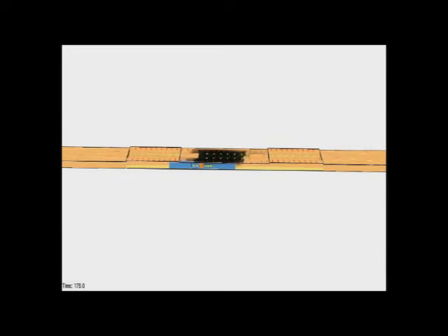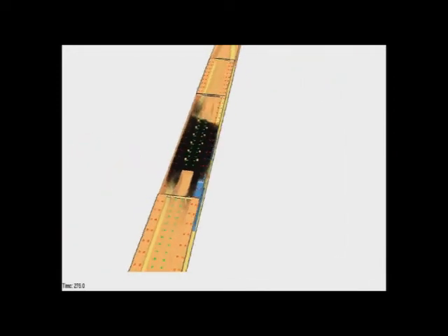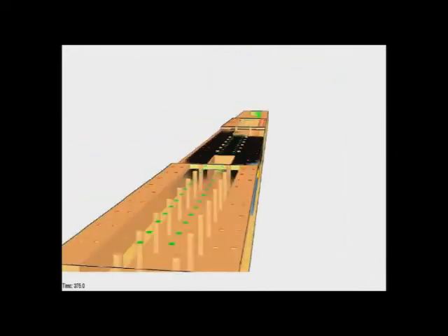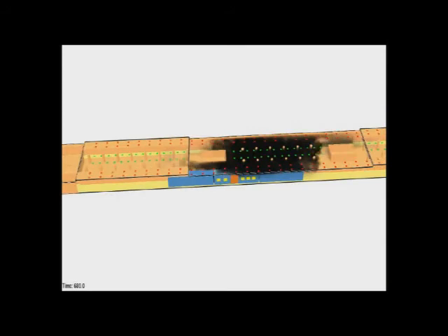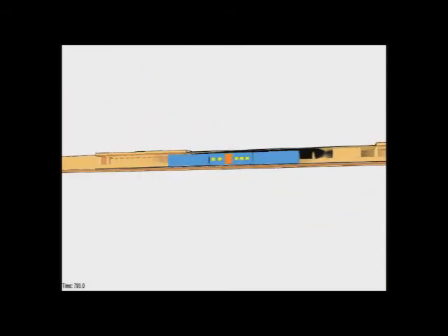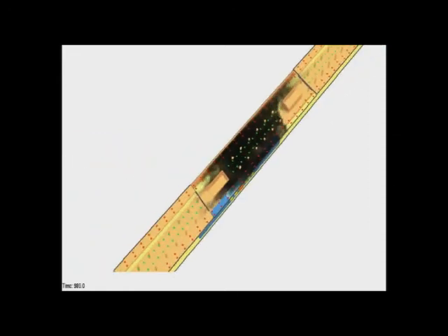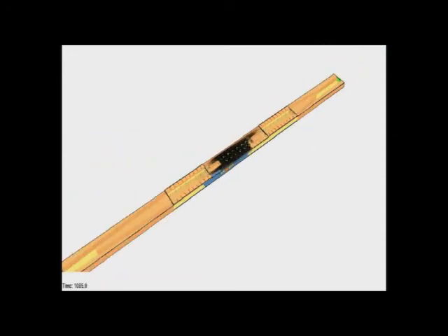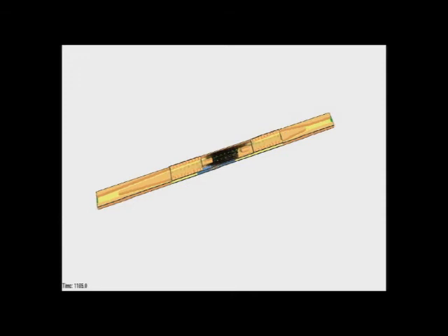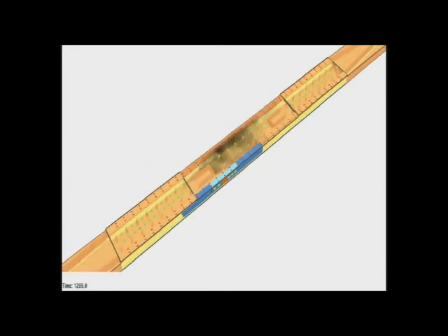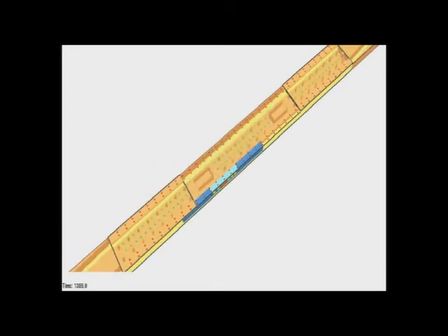We came up with this design and we did the simulation. In the simulation we could see that this is much faster. It's already 300 seconds. The visualization is much faster. You can see that this whole area was covered in smoke, and there was almost zero visibility in this area. So people will be trapped in here due to this. So this case was obviously not approved.